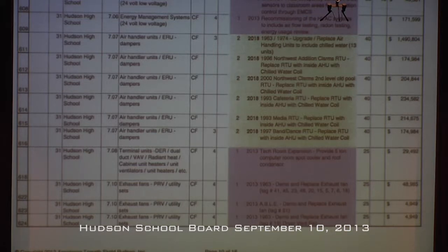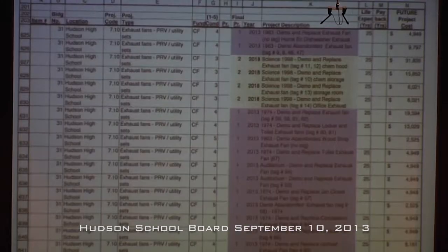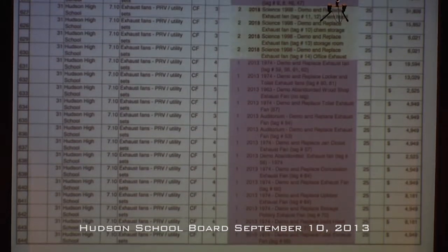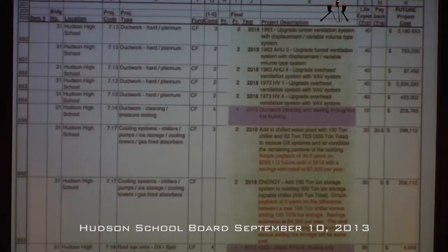We also have quite a few items. If you look on page 11, we'd like to replace all the exhaust fans on the roof. Those are all original. They're all ready to be taken off and replaced. They're all on their last leg. On page 12, item 650, we'd like to upgrade the tunnel ventilation system and duct all of that. It's now currently a big plenum, which means it just blows around the tunnel. We'd like to contain it within ductwork, and that's a pretty large number.